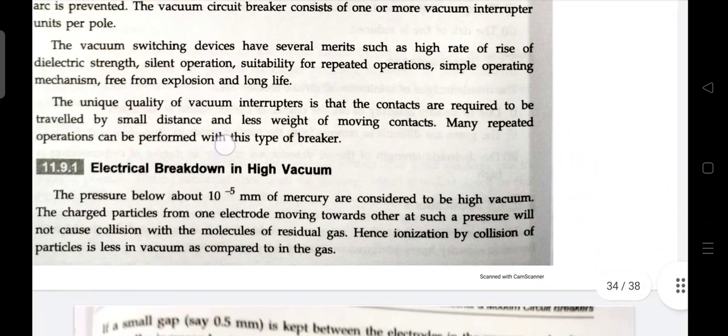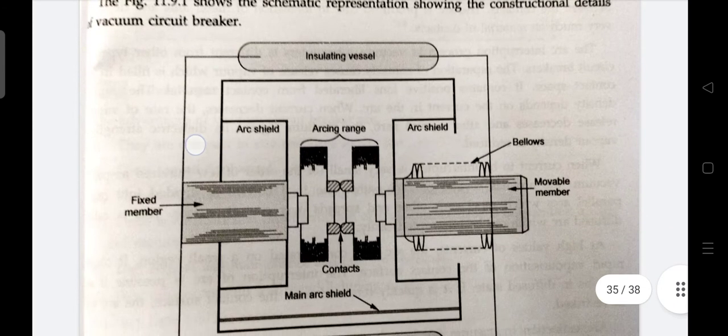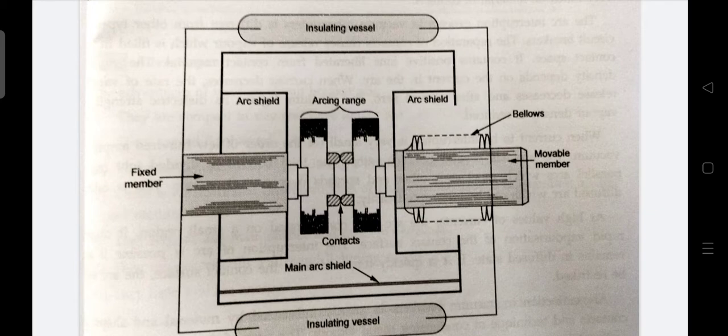Here the medium which we will use for arc extinguishing will be vacuum. In vacuum circuit breakers, the degree of vacuum being in the range from 10^-7 to 10^-5 torr is used as the arc quenching medium since vacuum offers the highest insulating strength. It possesses far superior arc quenching properties than any other medium.